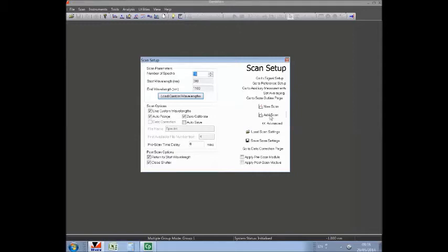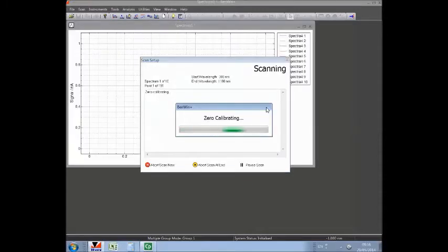So now we've selected 10 scans and we select new scan, and we'll let power on now the CL6 at 6.3 amps with red-black leads and fan connected. As I say, the lamp is now having a warm-up time during which we're doing scans, and we can now go and do some other task. The zero calibration information will be reported in a short time. Here we're employing 2 detectors, the photomultiplier and the silicon photodiode, which will be reported, and the scan will commence.